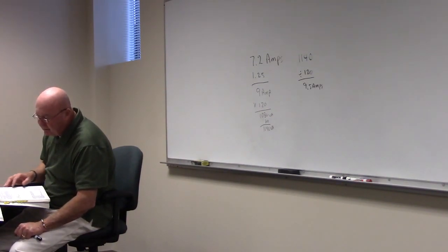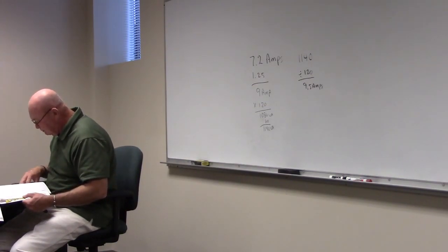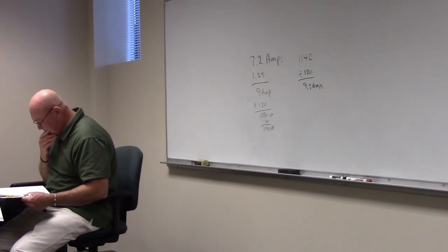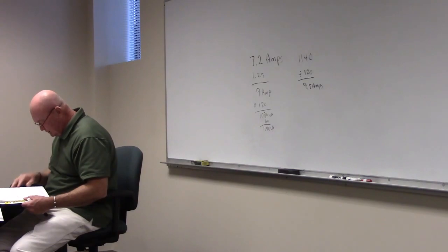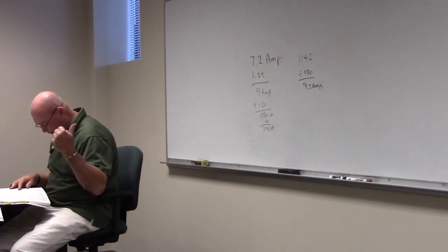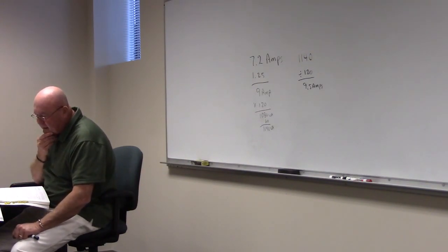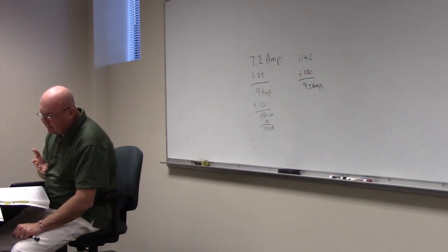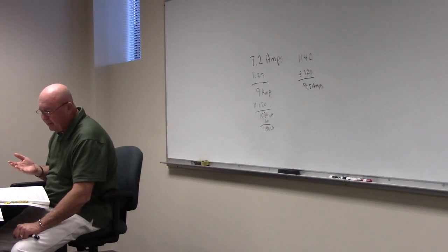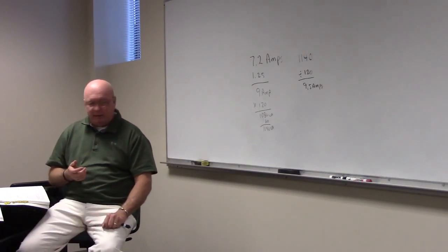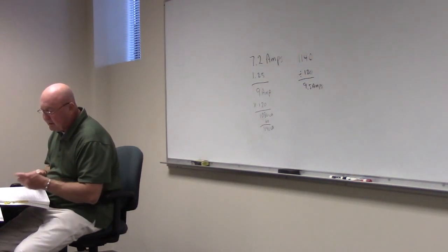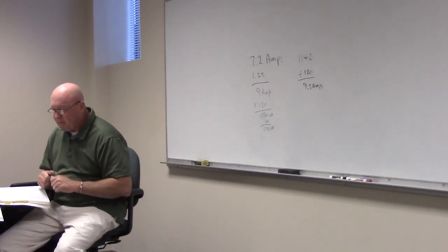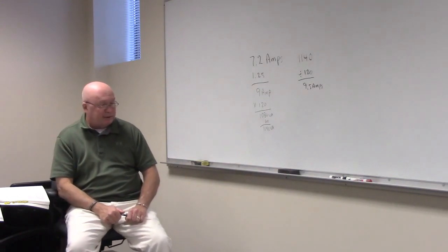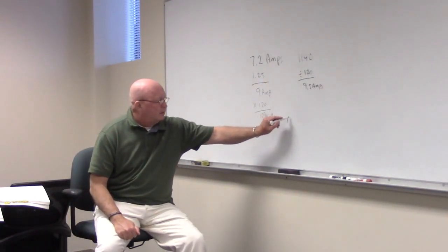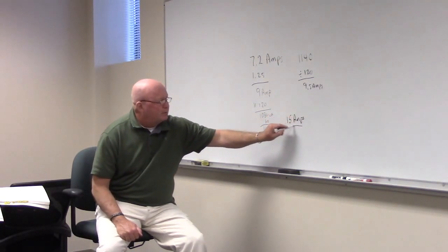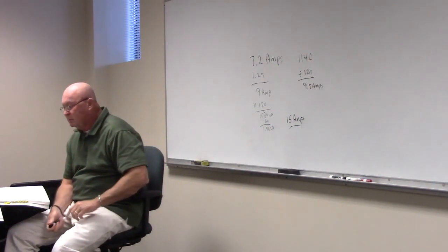Section 230.79, okay, that's 230.79. Rating of service disconnecting means. Service disconnecting means shall have a rating not less than the calculated load, which is what we've done, okay? All right, and so the service entrance conductors have an ampacity of not less than the load to be served, okay? And so what would our, now let's think about this. What would our disconnecting means be then? If we've met these requirements, whatever the disconnecting means would be. It'd be 15 amps, wouldn't it? That would be our next higher common size that we'd use.